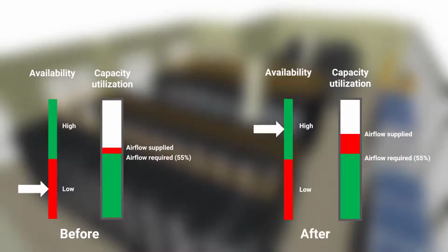This configuration was using 91% of the available cooling to support an IT load that was only 45% of the available power. And this highlights the problem. Current tools and techniques lack the capabilities needed to account for data center behavior and performance.